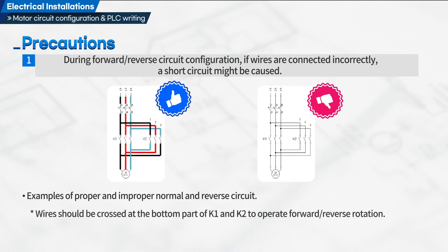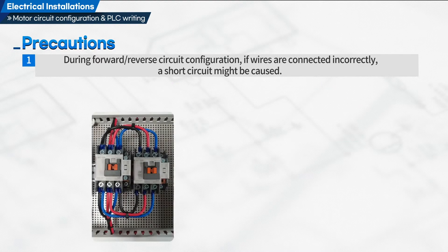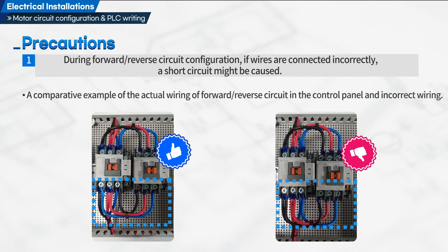Examples of proper and improper forward reverse circuit. Wires should be crossed at the bottom part of K1 and K2 to operate forward reverse rotation. A comparative example of the actual wiring of forward reverse circuit in the control panel and incorrect wiring is shown.